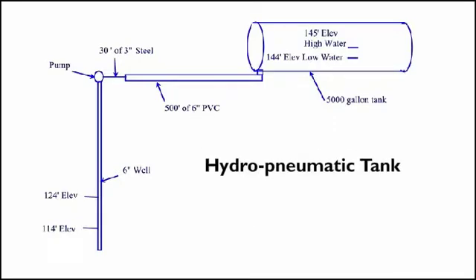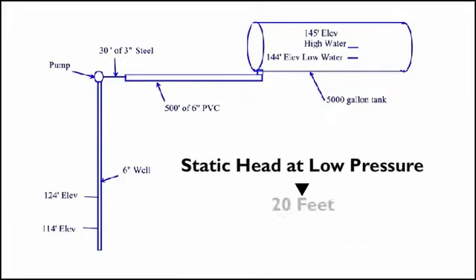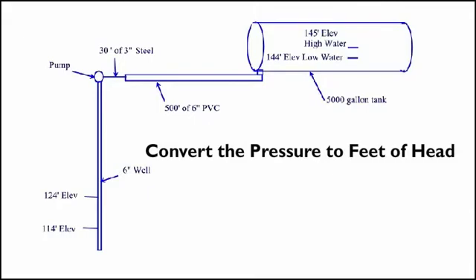The hydropneumatic tank is set to be at a water elevation of 144 feet at the low working pressure of 45 pounds per square inch. Thus the static head at low pressure would be 20 feet, which is 144 minus 124.